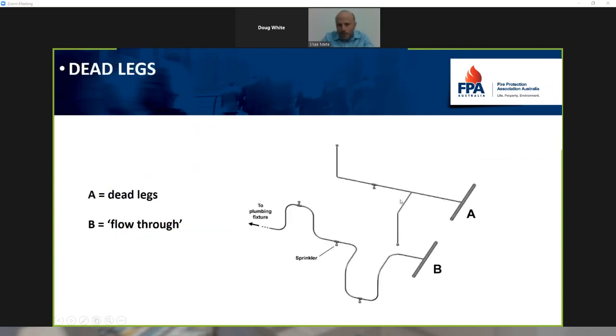But just a schematic here. So typically sprinklers are fitted in the way that A demonstrates here with these dead legs, whereas a flow-through design demonstrates that you can have this pipe flowing all the way through there and there's no dead ends.